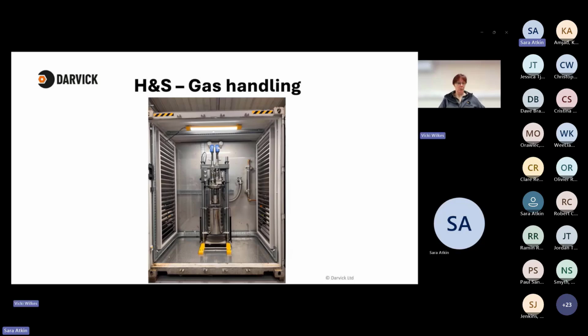There's a fairly simple solution to ensuring that you don't get too much hydrogen buildup, and that is ventilation. So this is an example of a machine we're building at the moment that will use liquid hydrogen, and it's going down to an airfield, and the real basic solution is very large vents in the side, so that if any hydrogen escapes out of that frame, despite all the safety features, it will disappear. It will not be able to build up to such a high level of concentration that it could possibly explode.